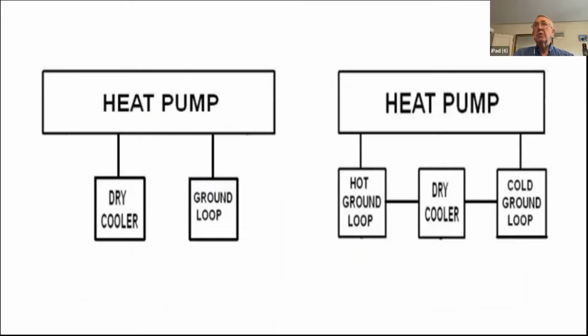And the example from Spain is shown here in a very crude way on the left. The heat pump has a choice of fluid, either from the dry cooler or from the ground loop, whichever is better at the time. On the other hand, the system from Belgium does not have the ability to have the dry cooler output going to the heat pump. What it does have is the ability to precondition either the hot loop on the left or the cold loop on the right. Now, wouldn't it be kind of good if we could combine these effects together in one system?